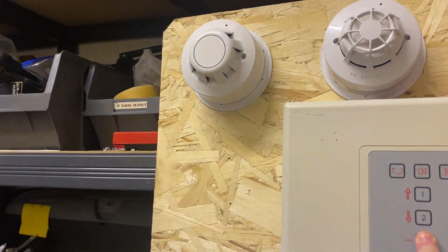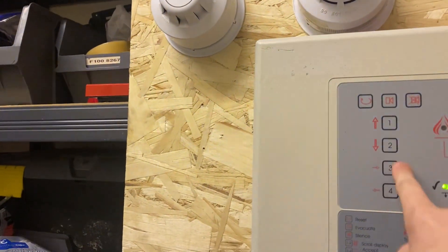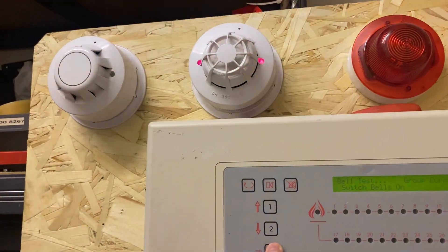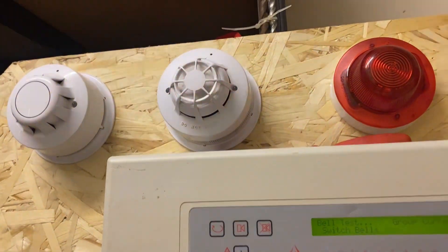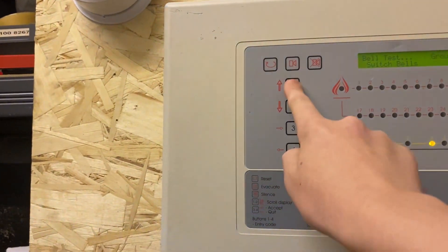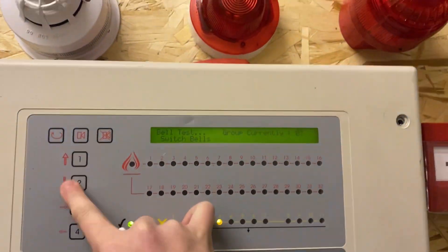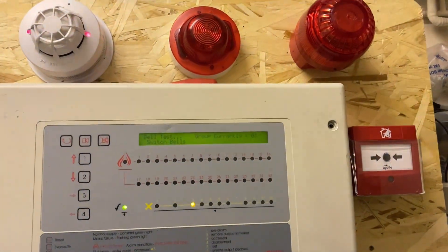Group bell test: group one is just the integrated group. Group two is the sounder beacon base — takes a little while. No tone hold, but it doesn't really matter. Group three is both of these together — nice little fake tone hold. Beacons aren't in sync for some reason; I have no idea why. Sorry about the flickering — it's that light.